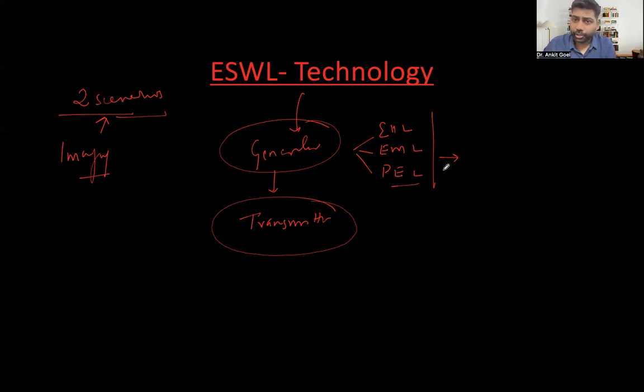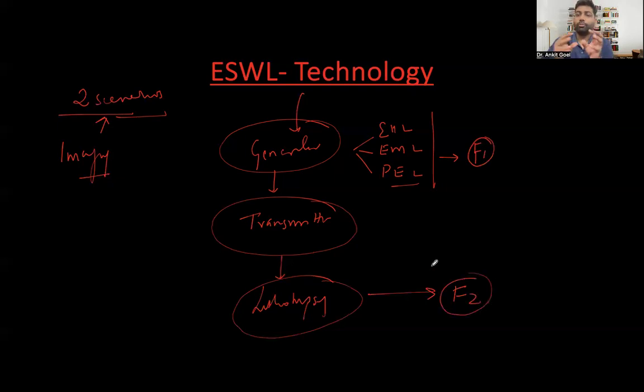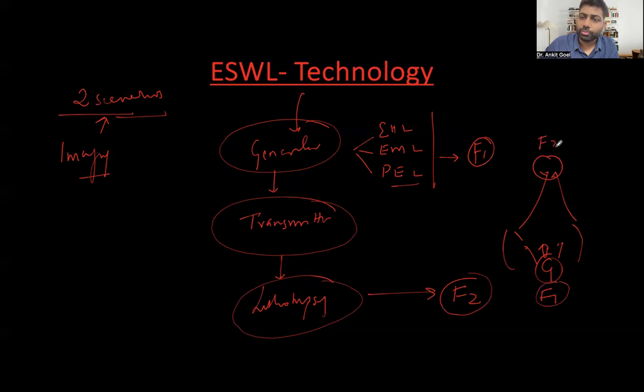The generator produces shock waves, and the area where all the shock waves emerge is known as the first focal point — F1. They are transmitted by a transmitter to be focused at the stone, which is at the second focal point — F2. This is straightforward. Even for Section 1 candidates, you're getting this in MCQs and single best answers. The transmitters are basically mirrors or reflectors, which reflect the energy generated by the electrohydraulic, electromagnetic, or piezoelectric mechanism to the stone.